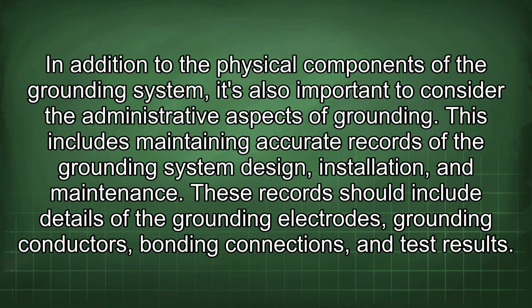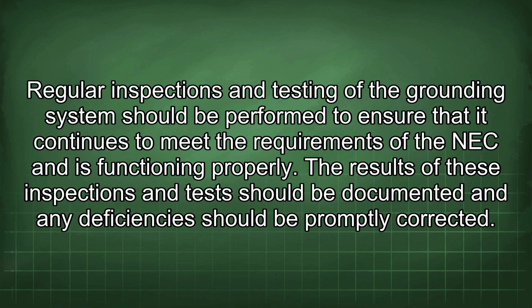These records should include details of the grounding electrodes, grounding conductors, bonding connections, and test results. Regular inspections and testing of the grounding system should be performed to ensure that it continues to meet the requirements of the NEC and is functioning properly. The results of these inspections and tests should be documented, and any deficiencies should be promptly corrected.